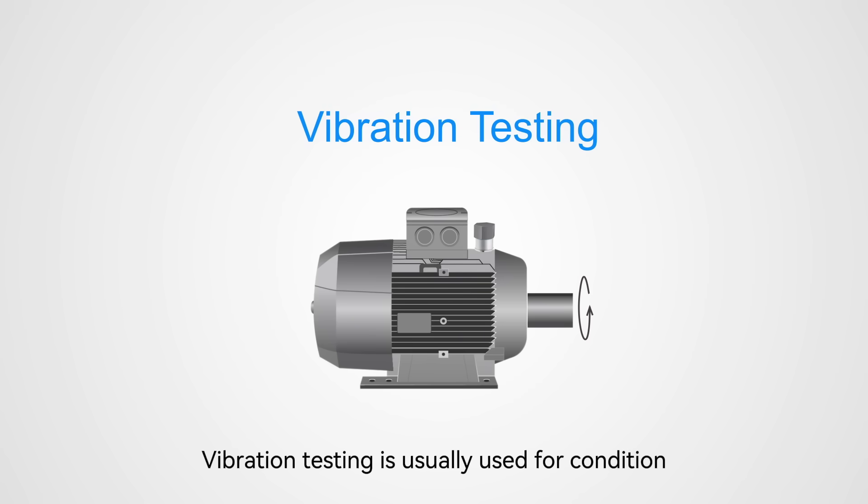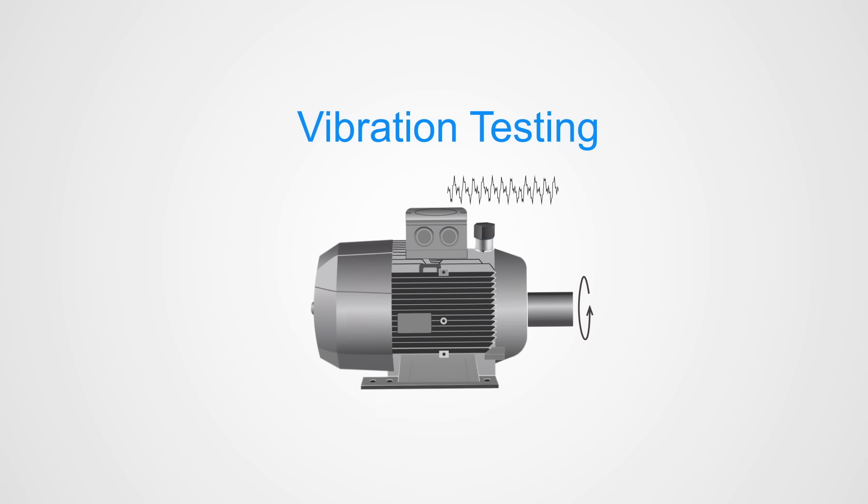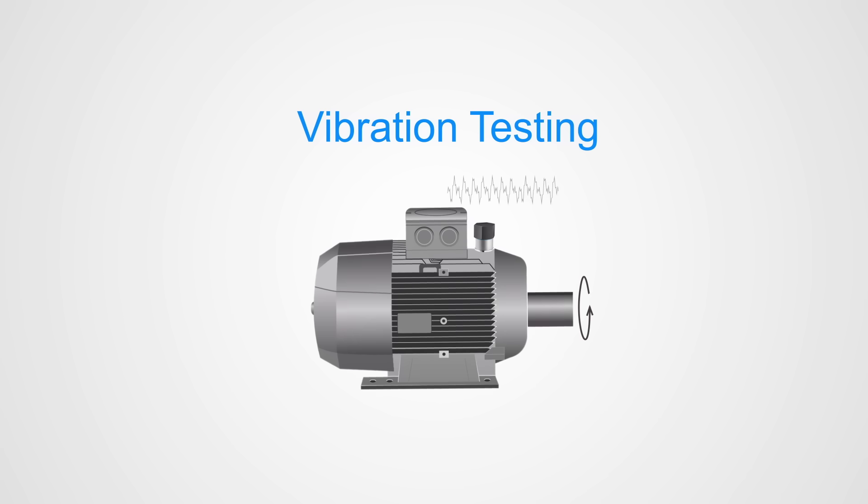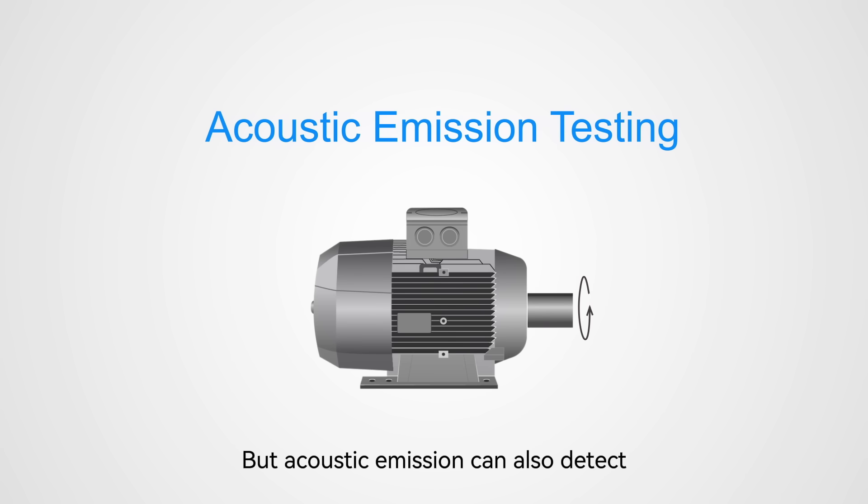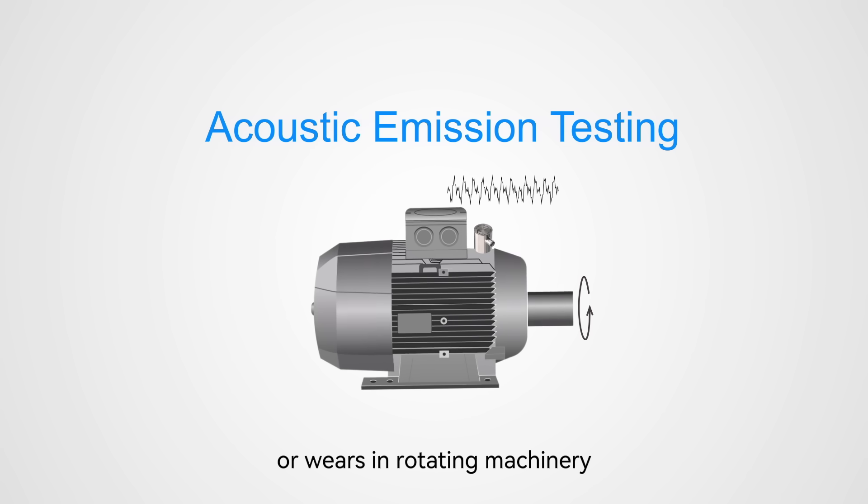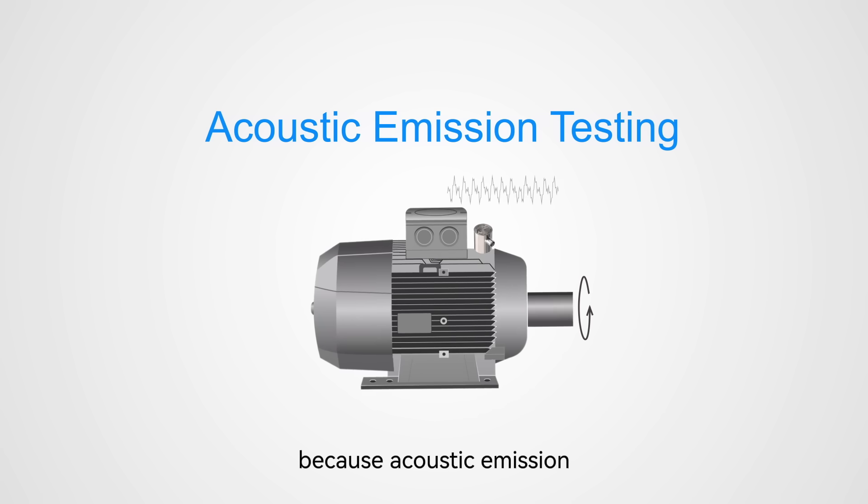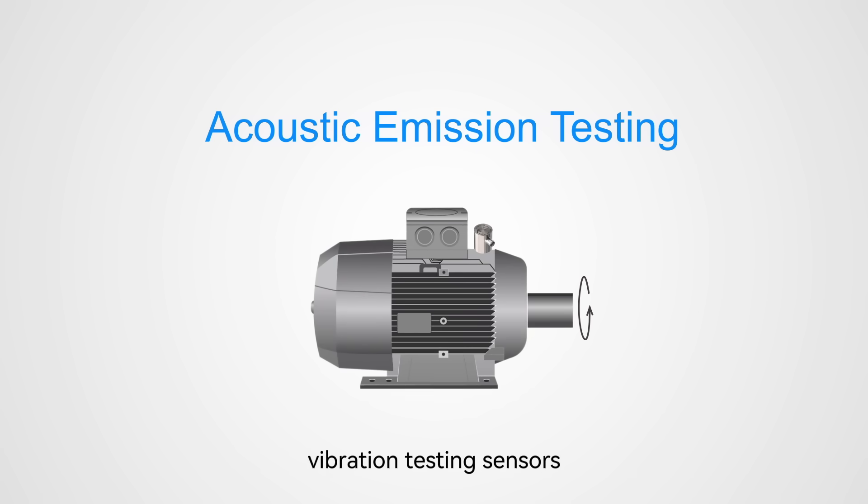Vibration testing is usually used for condition monitoring for rotating machinery, but acoustic emission can also detect earlier stage initial cracks or wear in rotating machinery because acoustic emission sensors have higher frequency range response than vibration testing sensors.